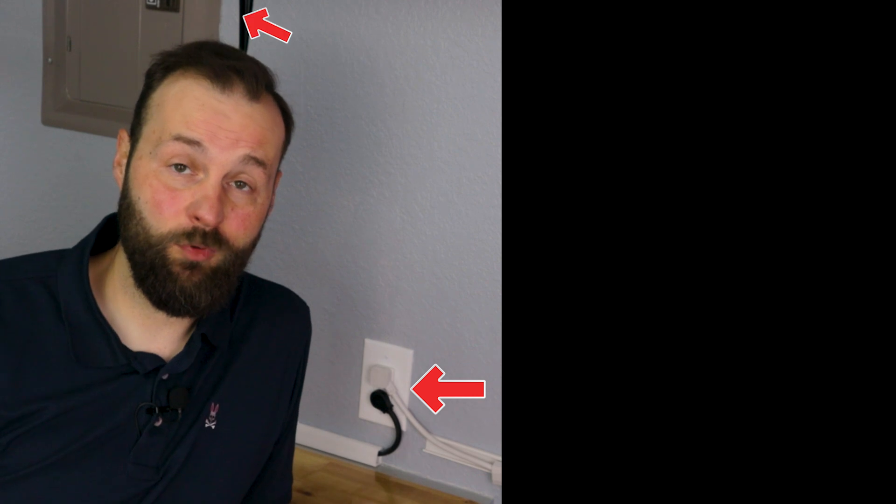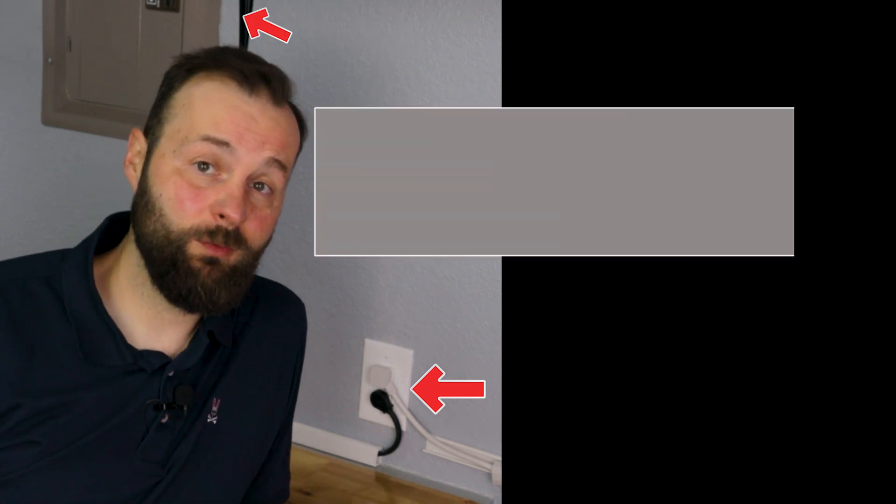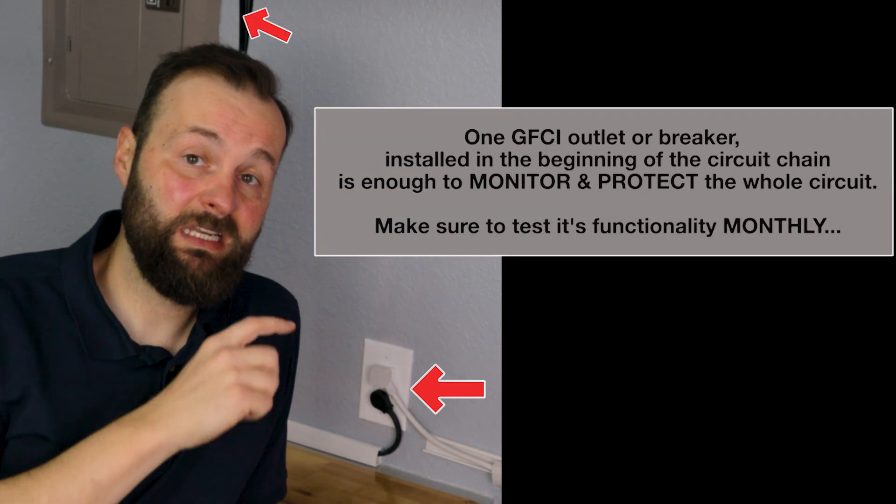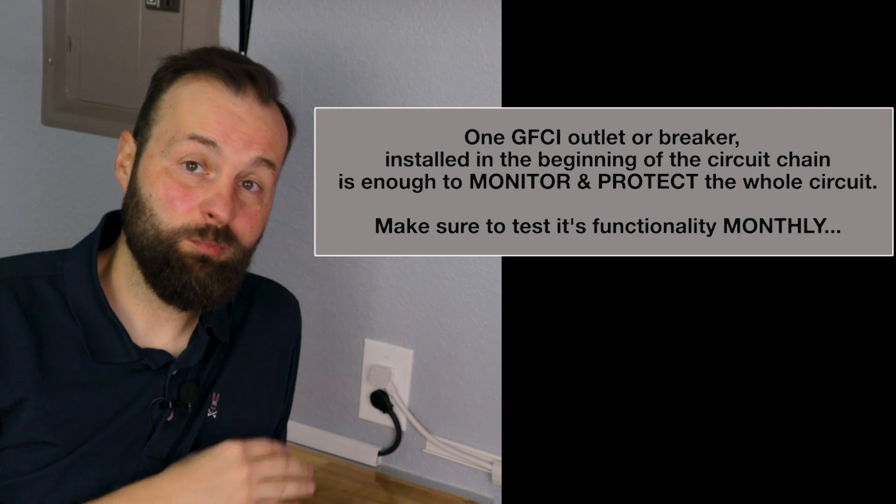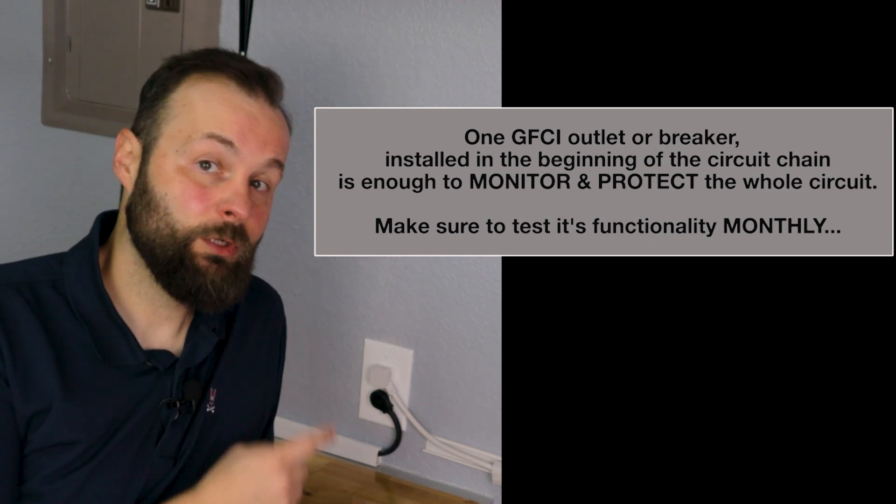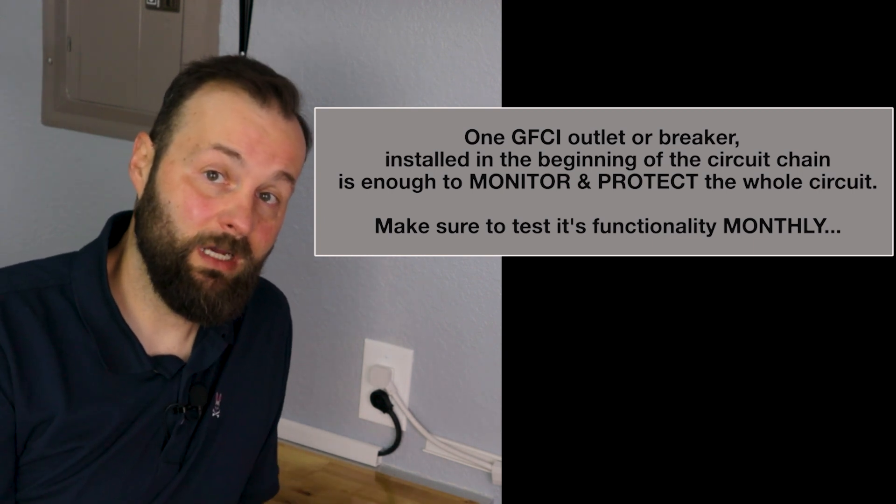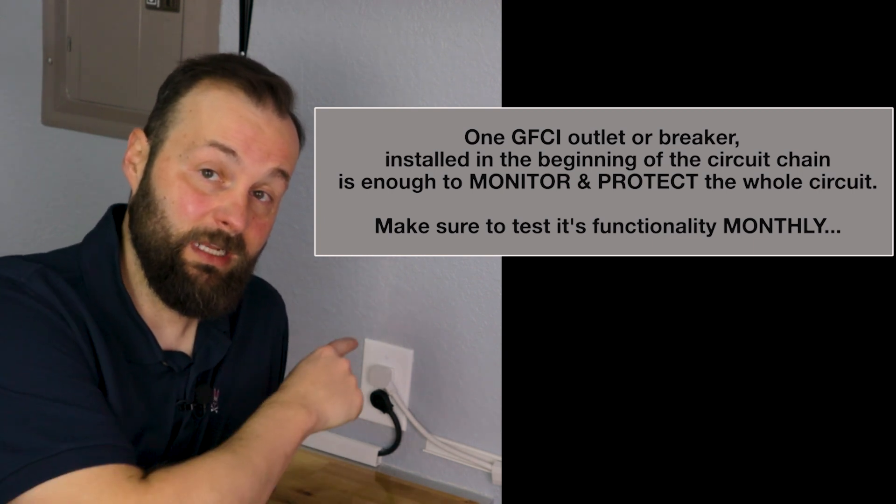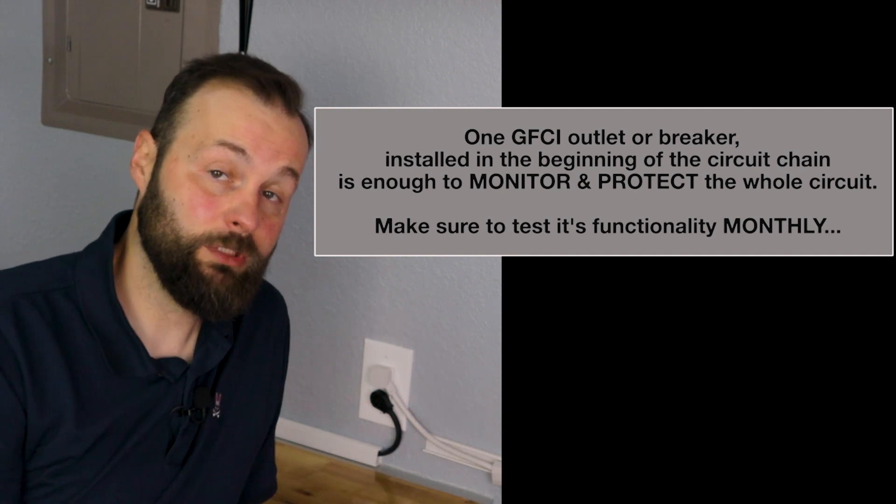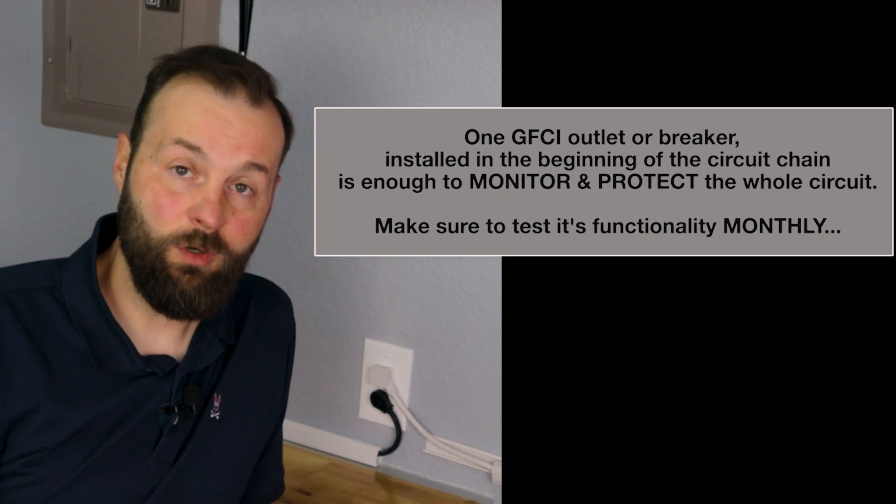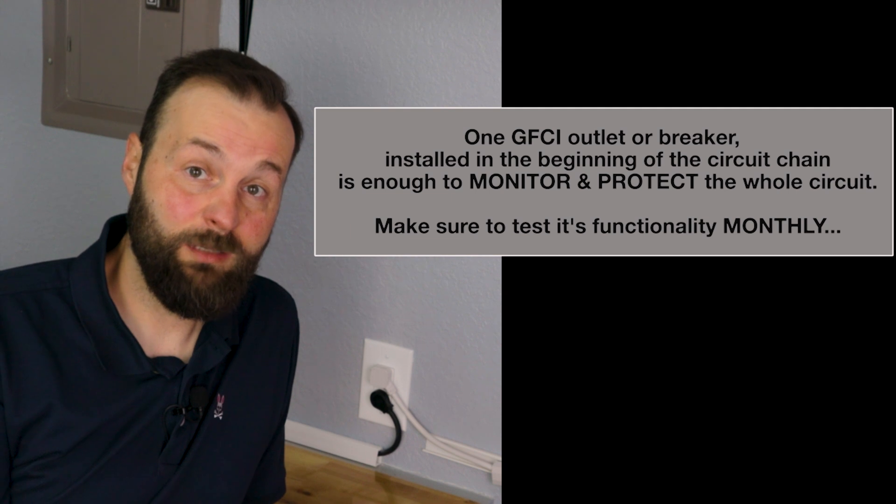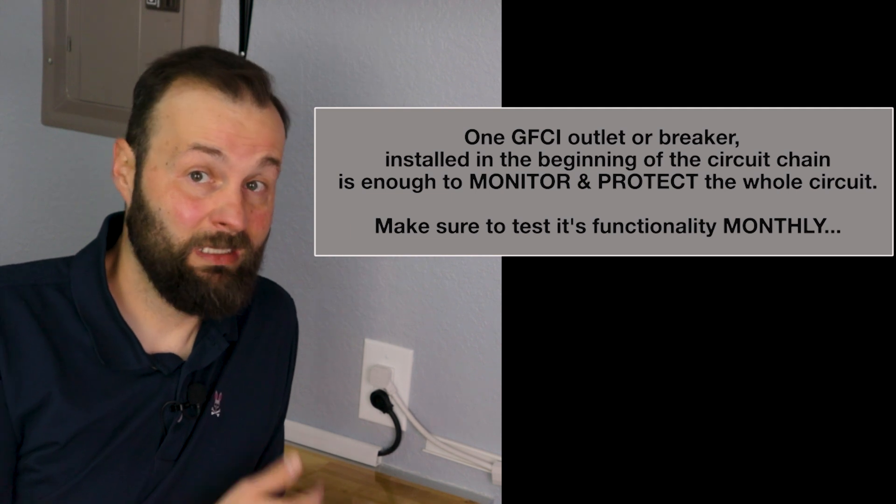Another great reason to install a GFCI outlet, especially if it's installed as the first outlet coming straight out of the circuit breaker before it feeds into other ones, is that if it is wired properly it will protect all of the other outlets. So if this one trips, all of the other outlets that are connected from this line will also stop working. So especially if your other outlets are not GFCI protected, put one in at the beginning of the line and the whole line is covered.